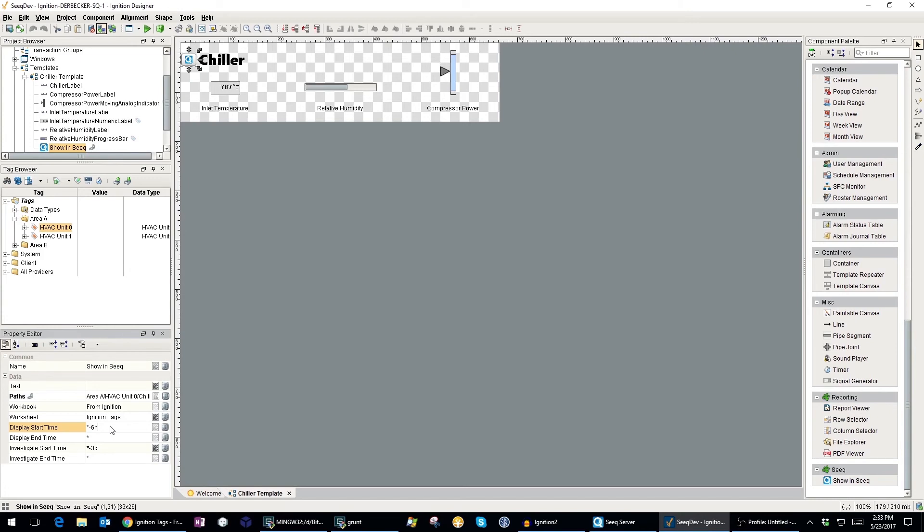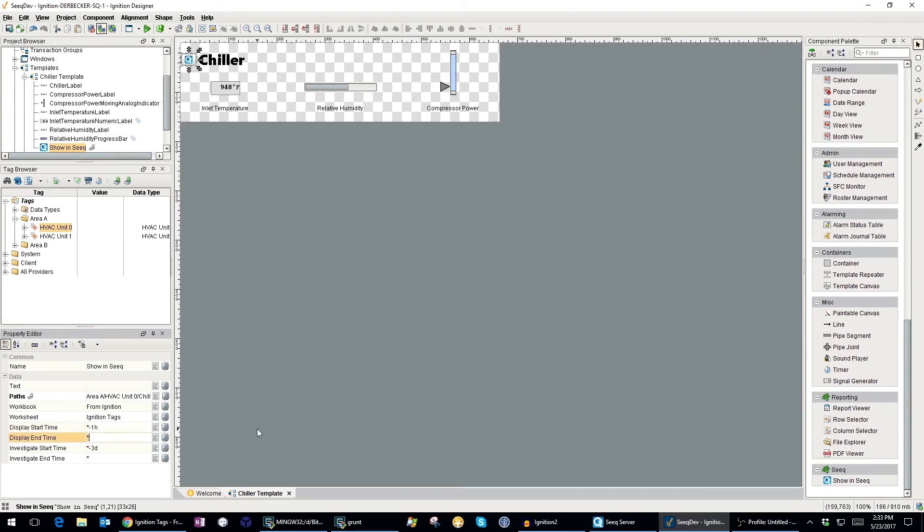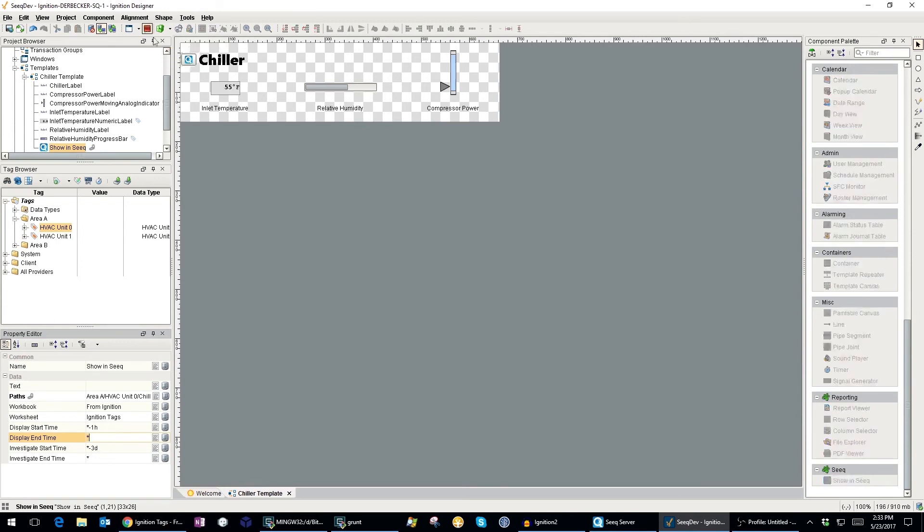For example, if I only want the last hour to appear in Seeq, I can set the display start time to star minus one hour. The star or asterisk is short form for current time. To try it out, I can put my template in preview mode and click on the button to launch Seeq.